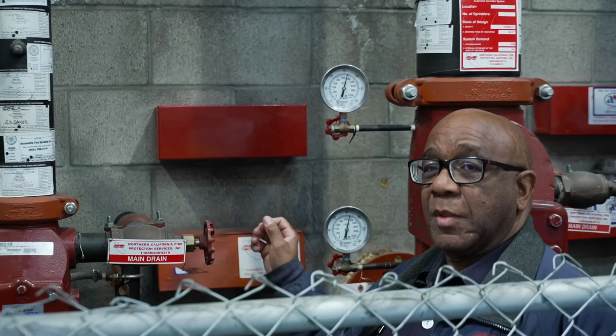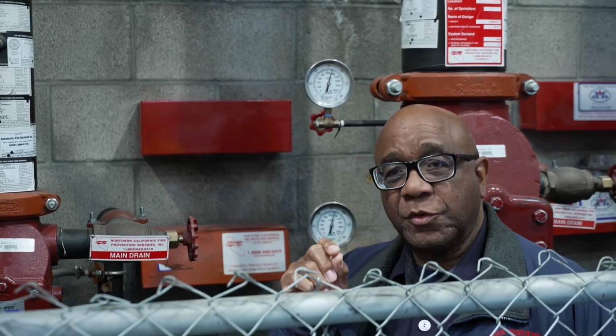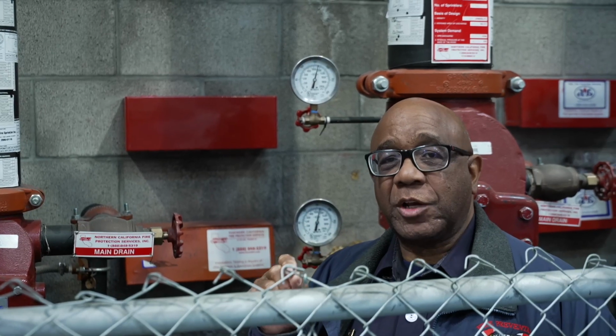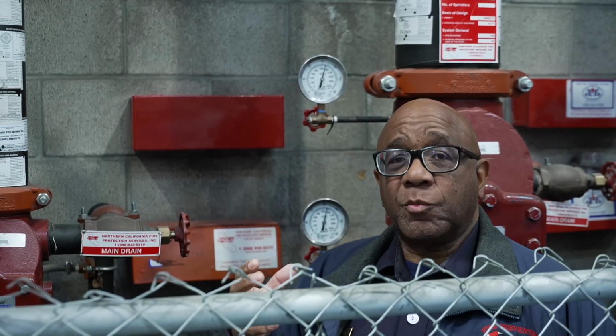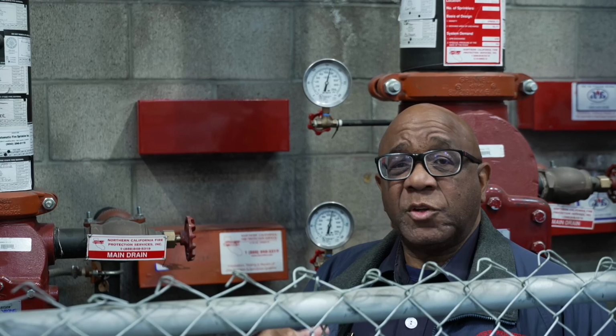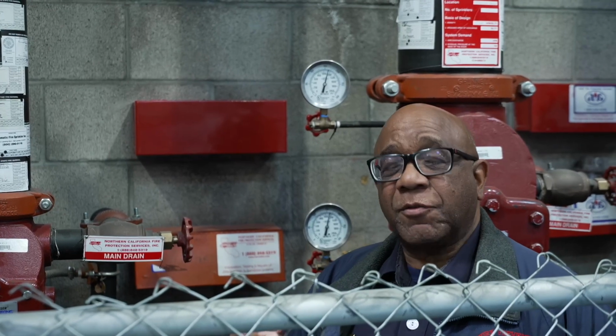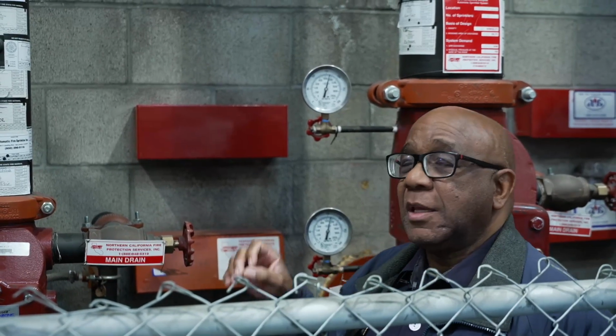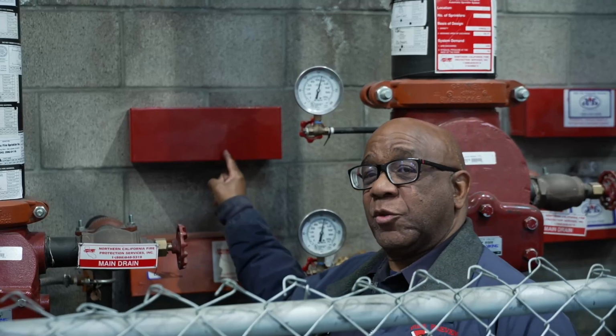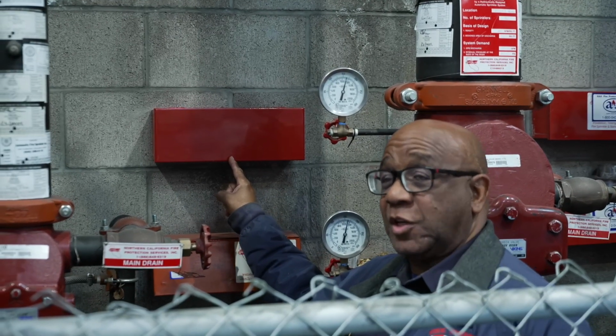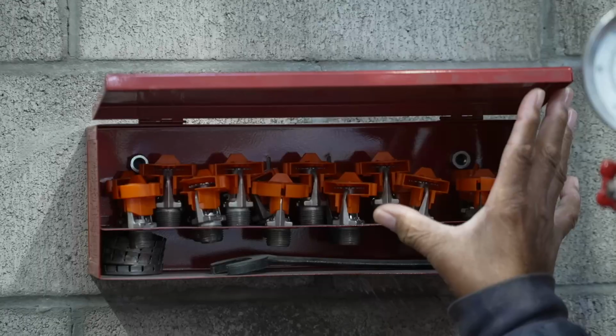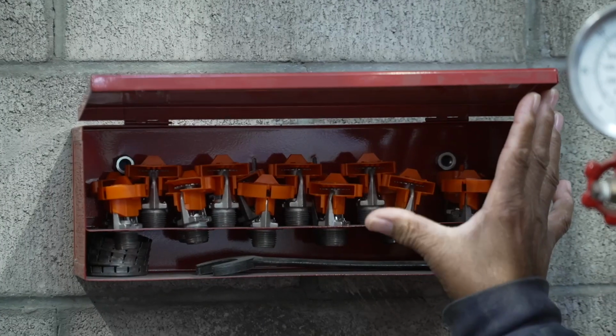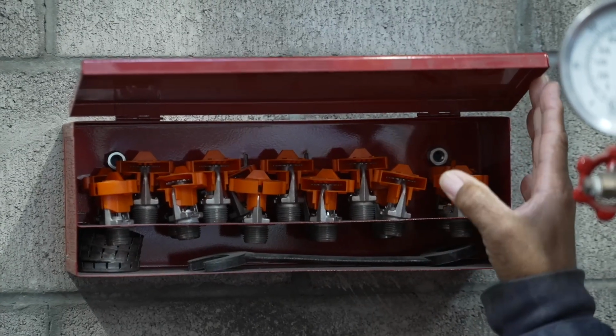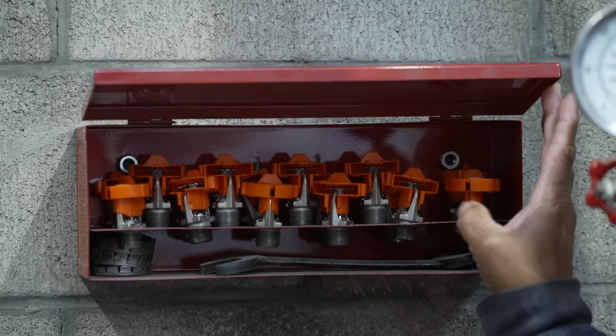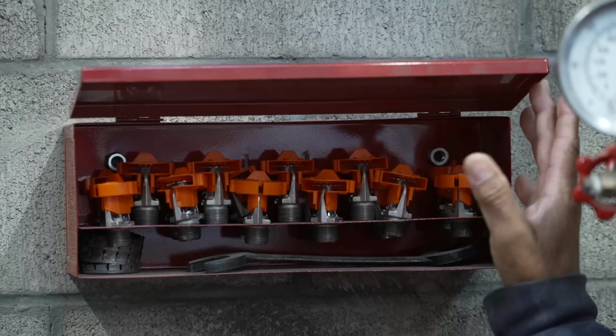Now, one of the things we have to always remember is to check the spare sprinkler cabinets. In a large mercantile occupancy, you may have between 4 and 7 different types of sprinkler heads. Each of them is going to have a spare sprinkler cabinet of this style. Inside the spare sprinkler cabinet, you're going to have a wrench. You're going to have the various types of sprinklers that are used for that particular system.